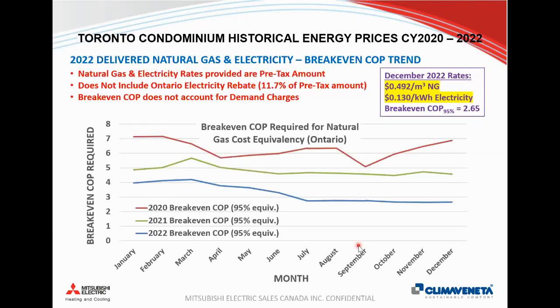Last thing on this that I find interesting is the break-even COP. Obviously, your rates fluctuate. Whenever you have less usage in the summer, your natural gas pricing is higher. But this red line at the top is the 2020 rates, and 2022 is the break-even COP that's needed based off the 2022 rates. So over time, we're seeing this break-even COP that you need from a heat pump getting lower and lower. And as of December of 2022, that break-even COP was 2.65.